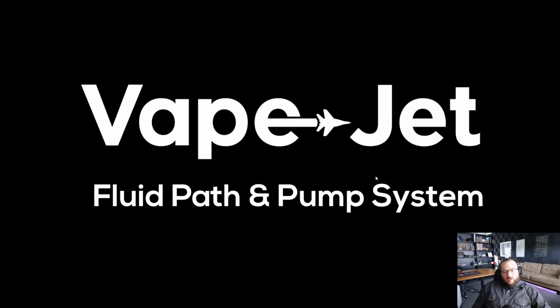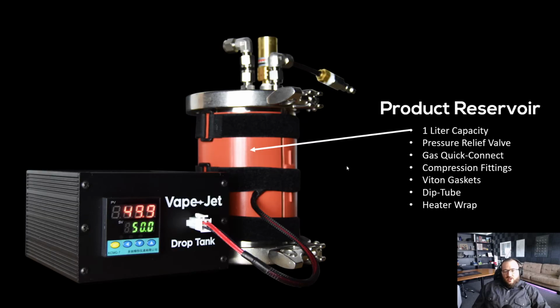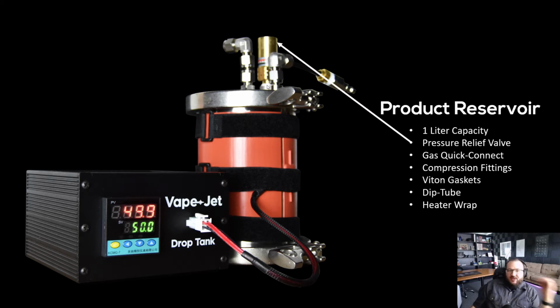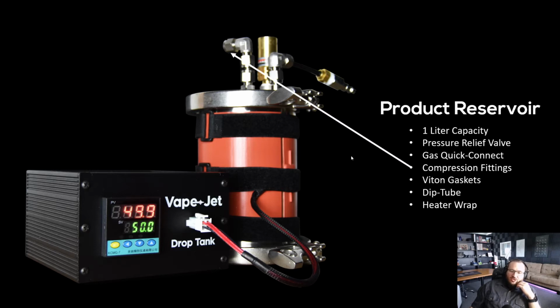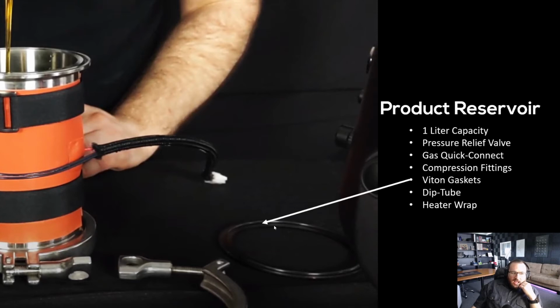All right. So let's do a deep dive on the fluid path and pump system. As we were talking about earlier, this is the product reservoir. It's a stainless steel reservoir with tri-clamps on top and bottom. There's a pressure relief valve at the top for safety reasons. A gas quick connect fitting to attach the nitrogen to, which we use to pressurize the system. The fluid output is a standard compression fitting. Inside the tri-clamps we provide Viton gaskets.